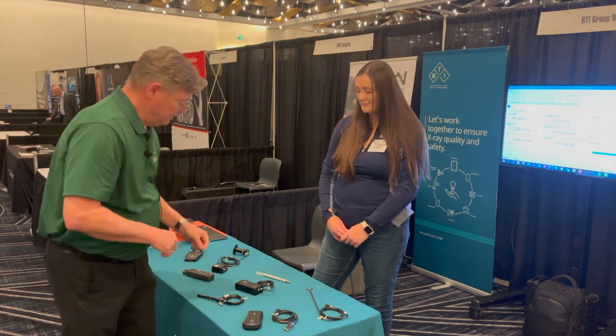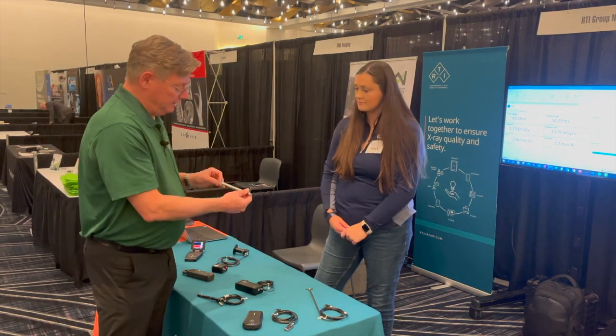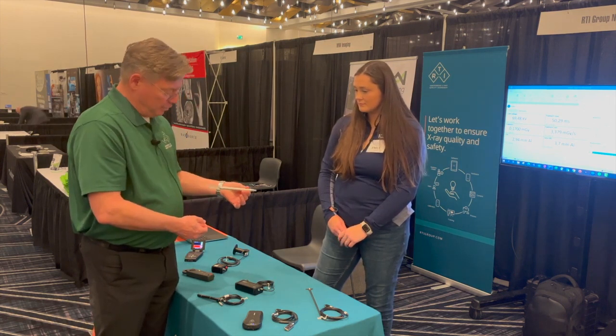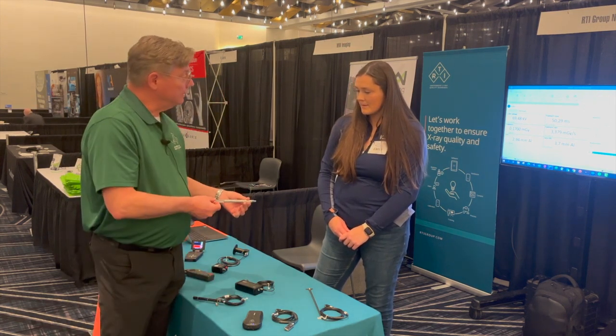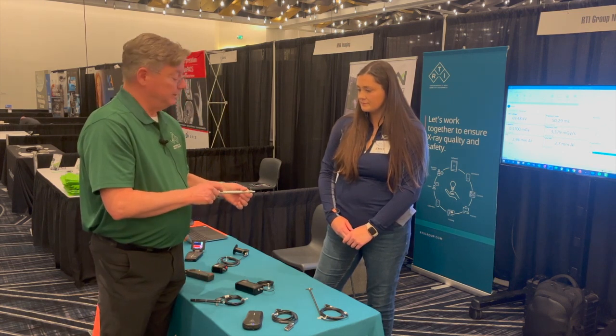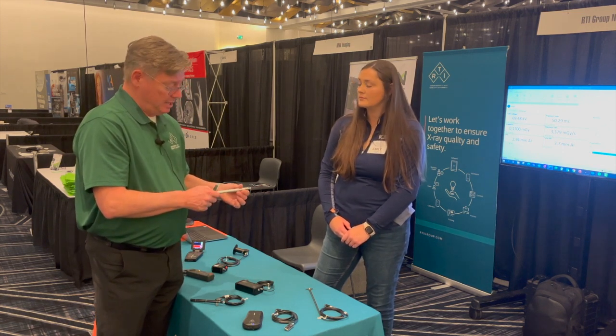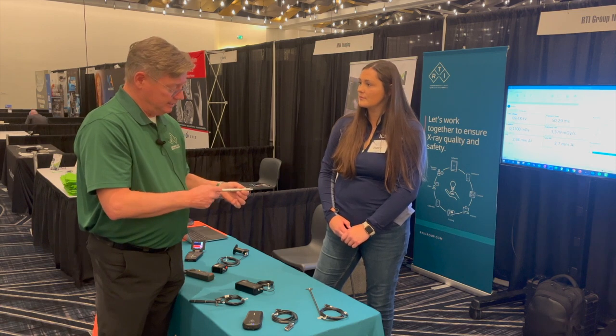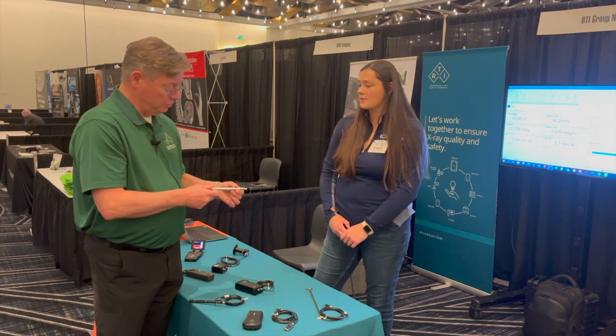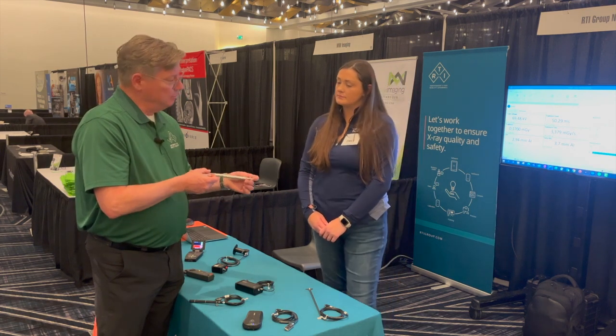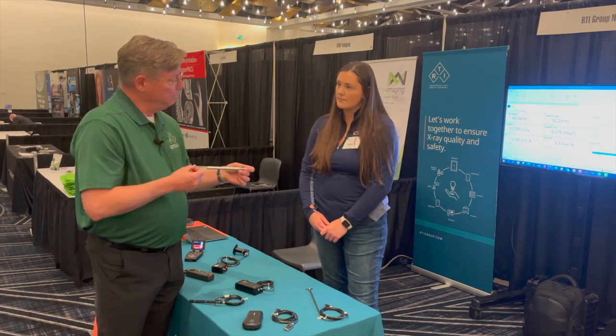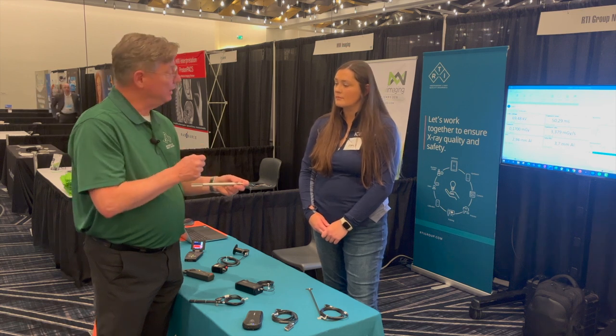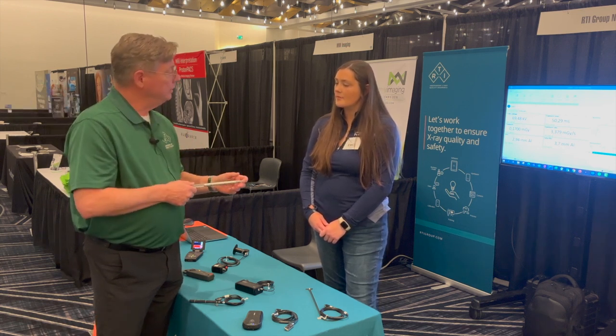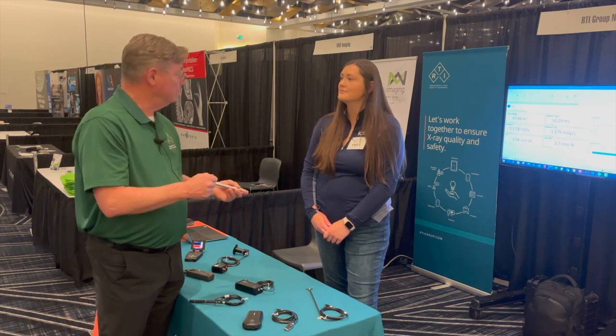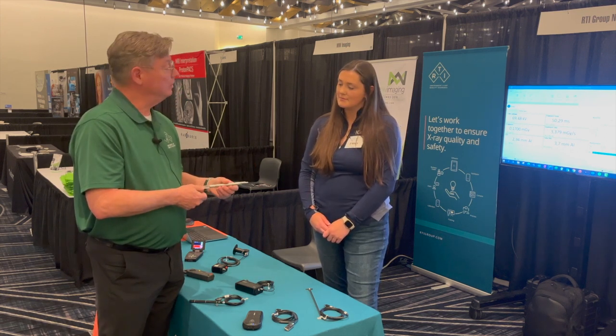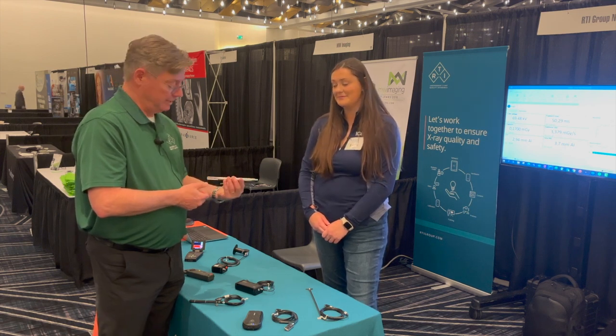In the console. Wow. And so continuing with CT, we've got a CT dose profiler. Looks like this. Looks like a pencil ion chamber, but it's actually solid state. Okay. So it has a built-in point dose detector right here. That is 0.25 millimeters long, so that makes it a point dose detector. The idea is that if you move it through the beam at a known speed, and you know the sampling rate, we can recreate the dose profile. Okay. So thereby getting the beam width with an accuracy and a reproducibility of down to fractions of a millimeter. Wow. That's kind of interesting.